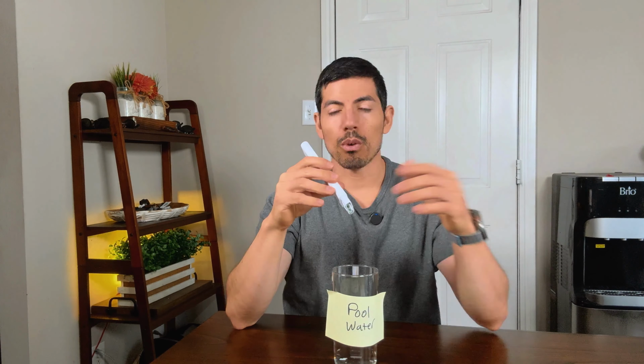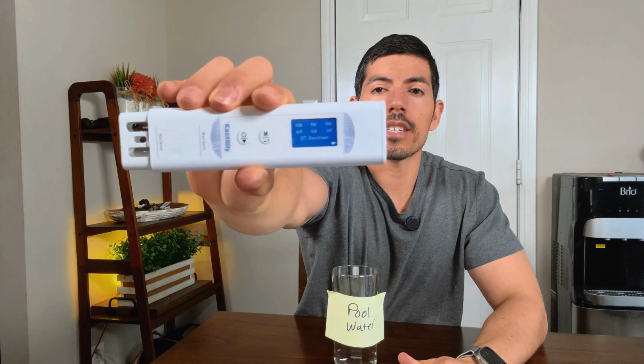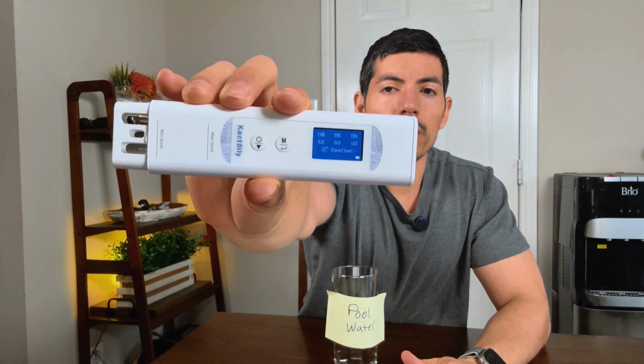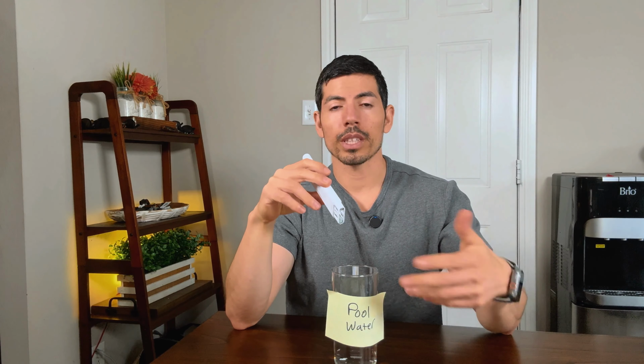But of course, pool water is not drinking water. So while it doesn't have a lot of total dissolved solids, on our meter here, we can see the TDS, total dissolved solids, is 182. And the COD and TOC are 0. So pool water is of course gonna have more TDS, total dissolved solids, because of the salt, the chlorine, the stabilizer. So this tester is really good at flagging dirty water, organic heavy water. It doesn't necessarily mean it's a green light to go ahead and drink. So always keep that in mind when using this tester.